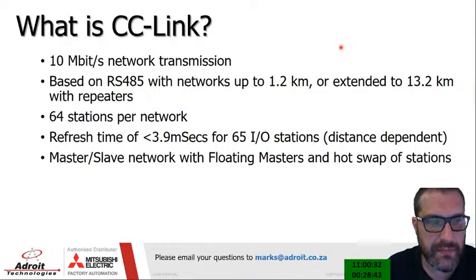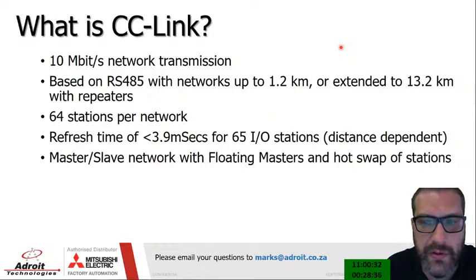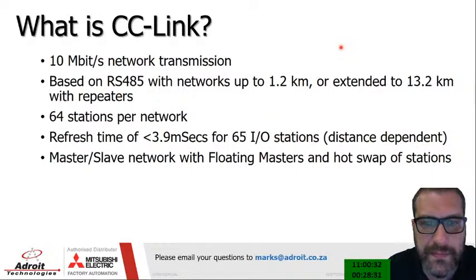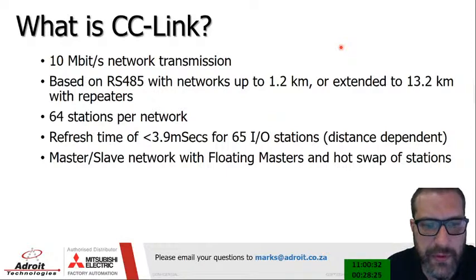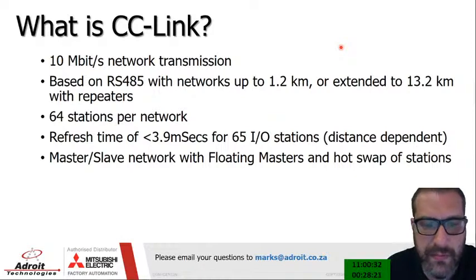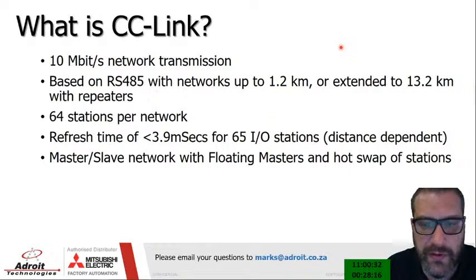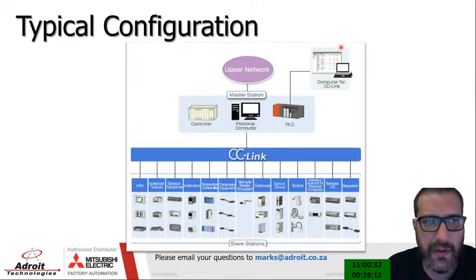CC Link is a 10 megabit network transmission based on RS-485, with networks up to 1.2 kilometers, or extendable up to 13 kilometers with repeaters. You can have up to 64 stations per network. The refresh time is less than 3.9 milliseconds for 65 IO stations, which is relatively fast. It's a master-slave network with floating masters and hot swap at stations.